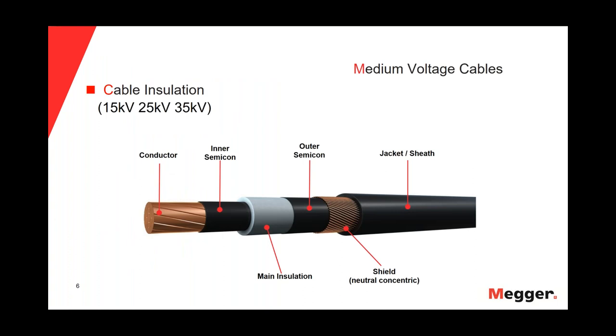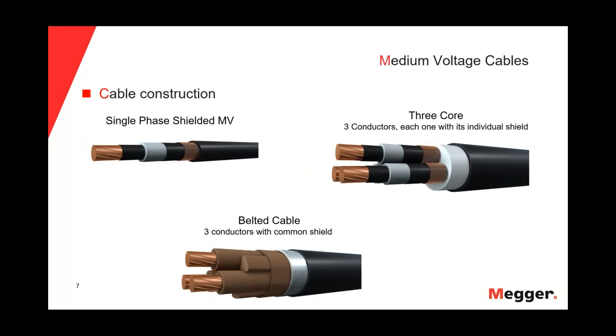Let's start with the basics for medium voltage cables. We are seeing in the slide the classic single-phase cable, which has a center conductor that could be of copper or aluminum material. Then we have the inner semi-con layer, the main insulation of the cable, and the outer semi-con layer. Next, we have the neutral concentric or shield of the cable, and finally the jacket or sheath of the cable. Regarding cable constructions, besides the single-phase shielded medium voltage cable, we can have the three-core cable in which we have three conductors each with an individual shield, and also the belted cable, in which we have three conductors but a common shield.